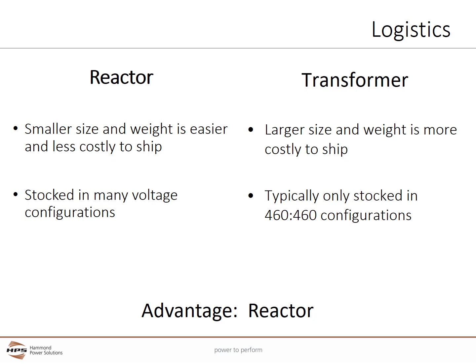Logistics. The logistical ability to get product quickly is important. Reactors are smaller and easier to transport. Reactors are typically stocked in North America to cover a number of popular voltages at either 3 or 5% impedance. Transformers are larger and can weigh 10 times or more than the equivalent reactor. They are typically only stocked in a 460 to 460 volt configuration, and other voltage configurations are typically made to order. Therefore, for their smaller size, weight, and wider stock base, reactors have a logistics advantage over transformers.